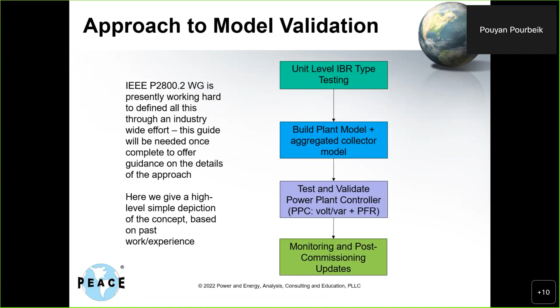So one more time, it's this kind of tiered approach: go through unit level testing, build the aggregated model for the large signal things you want to look at. Your best bet is to look at it with that accurate aggregated model. Then, for general volt-var response, primary frequency response, and future FFR, you can do that with field tests at the plant level. Don't forget about monitoring post-commissioning updates to keep track.